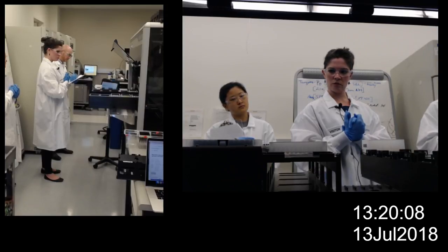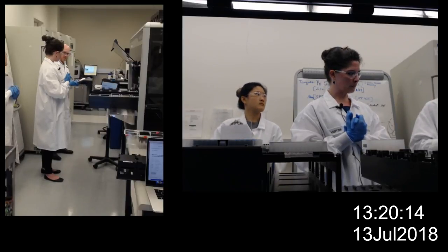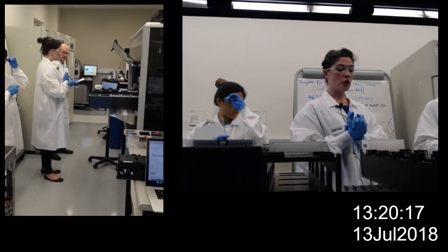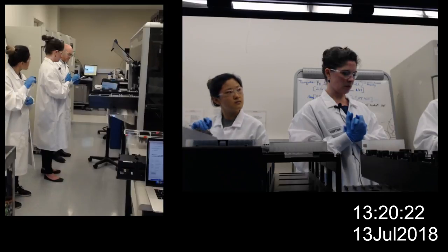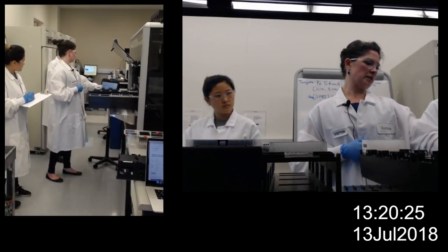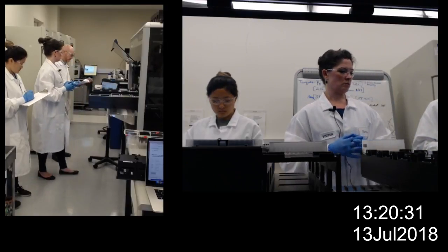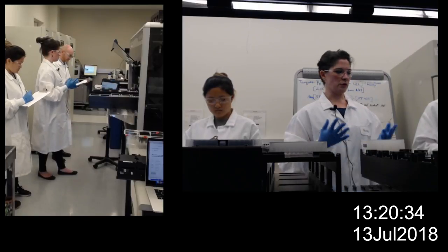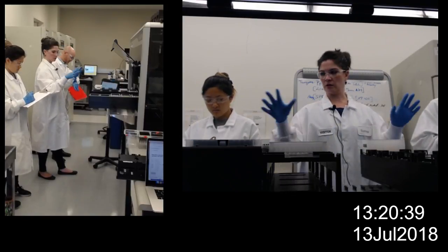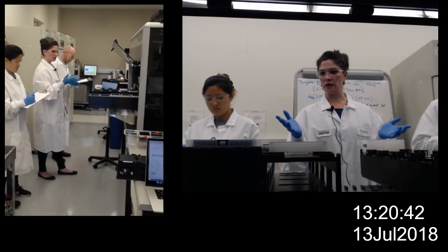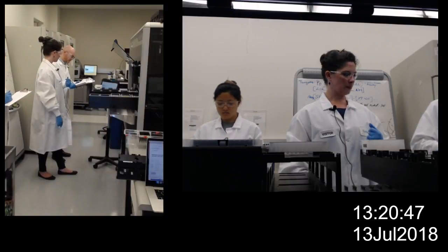Now everything else looks like it is where it should be. So you think that the representation is fine there? There's nothing that needs to be changed? No. I think the only thing I noticed off the bat was that all the carriers look the same regardless of their carrier type, and I was only telling them apart by what was loaded on them. Got it. I don't know if a visual difference in terms of tip carrier versus plate carrier would be useful or not, but if you're taking your time to double check your setup before you hit load, then you should find those issues anyway, like I did with the plate. Got it. Yeah, I captured that earlier when you said that.